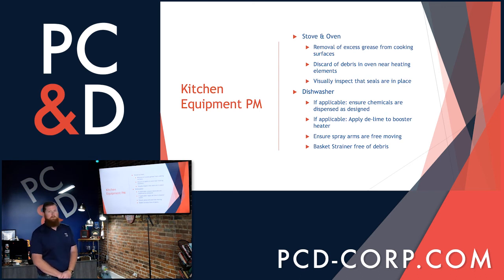Also, depending on where you're located in the United States, you may have a hard water situation and de-lime may be needed. That should be handled pretty frequently. In my professional experience, it's about every quarter that the equipment needs to be shut down for at least 12 hours and de-lime placed inside these areas to keep from any buildup taking place.